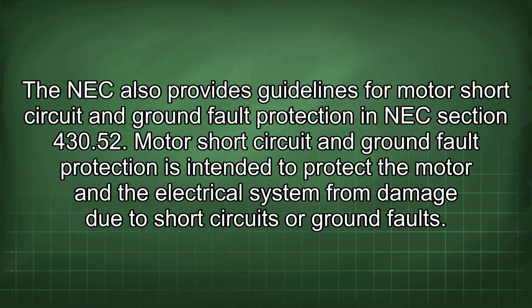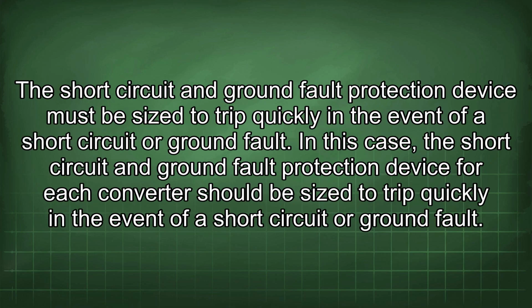The NEC also provides guidelines for motor short circuit and ground fault protection in NEC Section 430.52. Motor short circuit and ground fault protection is intended to protect the motor and the electrical system from damage due to short circuit or ground faults. The short circuit and ground fault protection device must be sized to trip quickly in the event of a short circuit or ground fault. In this case, the short circuit and ground fault protection device for each converter should be sized to trip quickly in the event of a short circuit or ground fault.